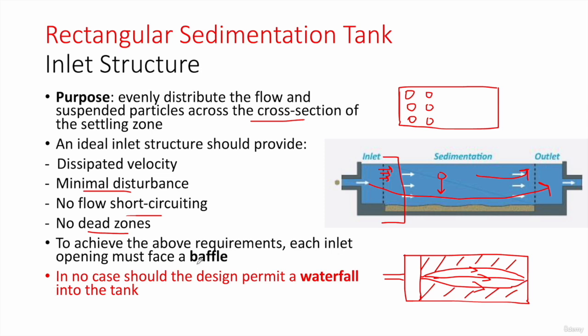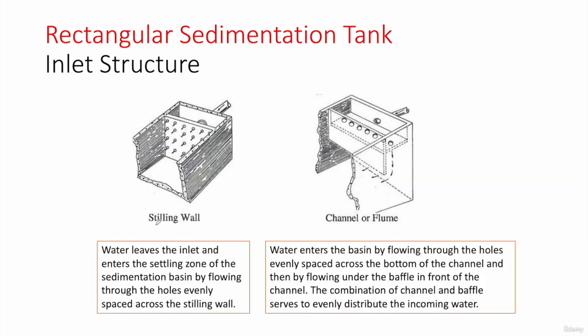To achieve these requirements, each inlet opening must face a baffle to distribute the flow equally. Also, an important note: in no case should the design permit a waterfall into the tank. We must avoid a waterfall at all costs because it creates turbulence in the water and highly affects the efficiency of the sedimentation process.